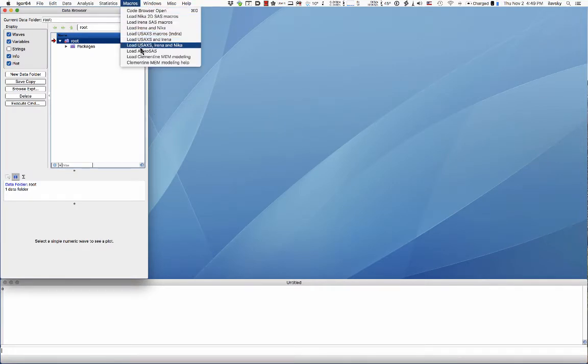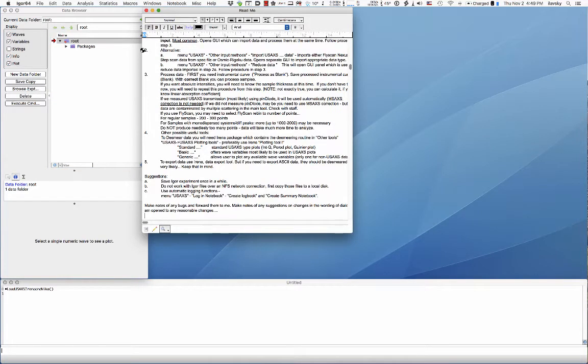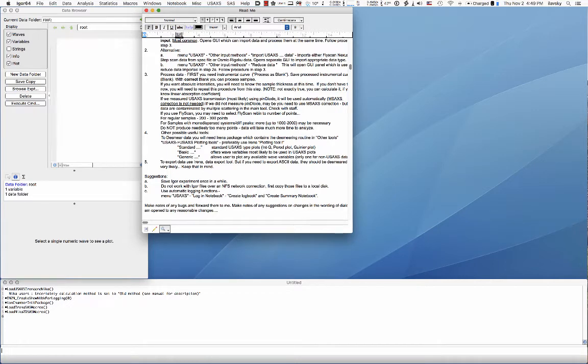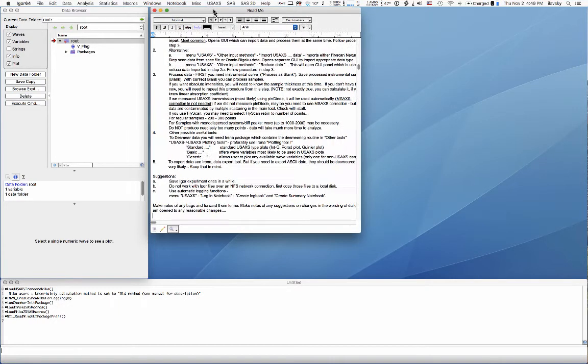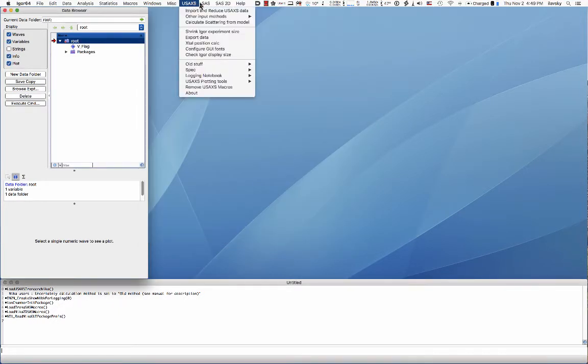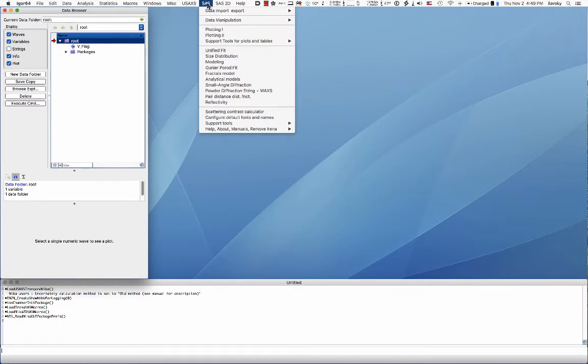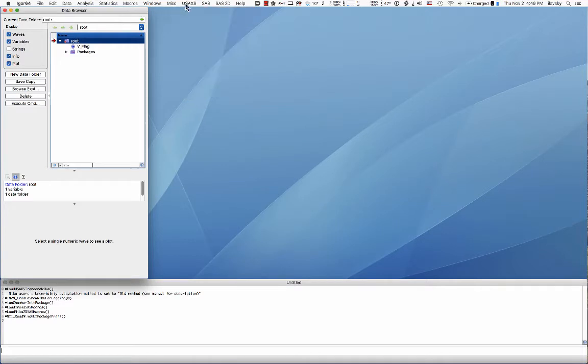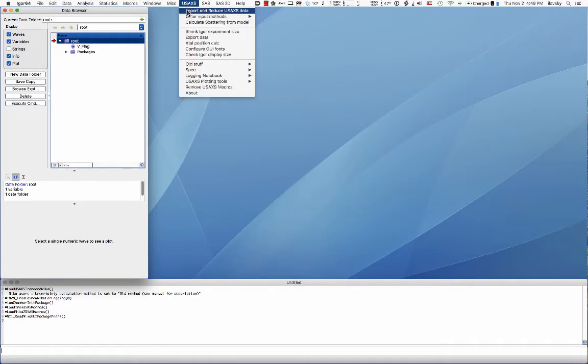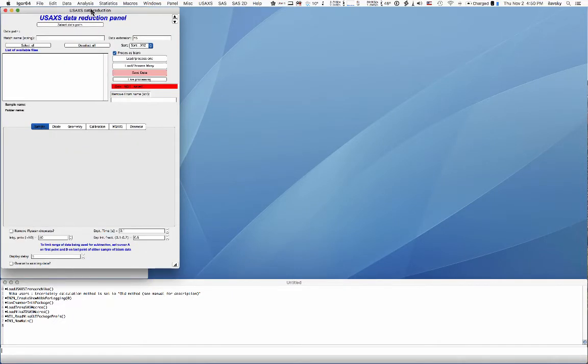We are in Igor and we're going to load USAXS, Irena, and Nika. When you load the packages and let Igor recompile, you will end up with a readme for USAXS and you'll have SAS and SAS2D menus. SAS is USAXS data reduction and SAS2D — the Nika package — is the SAXS and WAXS data reduction. What we want to do first is a reduction on USAXS data. It's not totally critical to do it in this order, but it's helpful. So you go to Import and Reduce USAXS Data, which opens a panel.